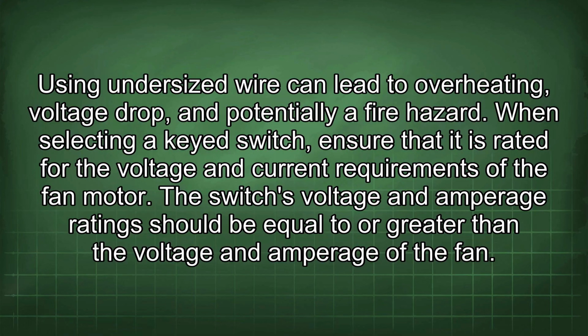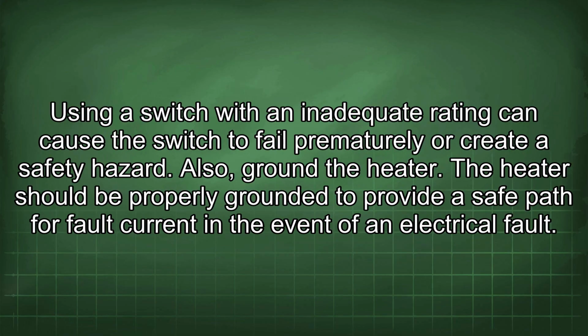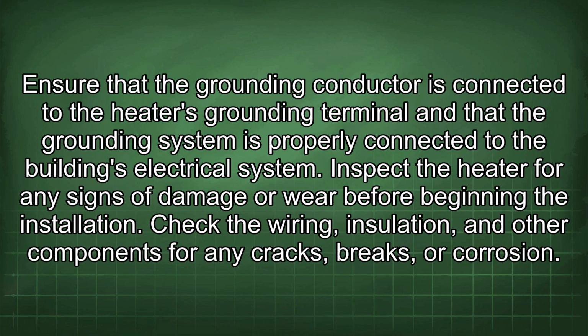When selecting a keyed switch, ensure that it is rated for the voltage and current requirements of the fan motor. The switch's voltage and amperage rating should be equal to or greater than the voltage and amperage of the fan. Using a switch with an inadequate rating can cause the switch to fail prematurely or create a safety hazard. Also, ground the heater. The heater should be properly grounded to provide a safe path for fault current in the event of an electrical fault. Ensure that the grounding conductor is connected to the heater's grounding terminal and that the grounding system is properly connected to the building's electrical system.